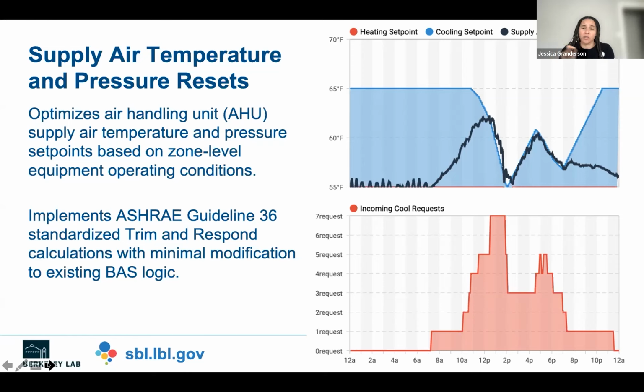The x-axis shows a 24-hour period of operation. And so what you can see is that when we hit that button and said, implement the best-in-class reset strategy, it worked. So you can see that as the cooling requests increase through the morning and into the afternoon, we're actually decreasing, kind of dropping that set point. And you can see how the supply air temperature follows.